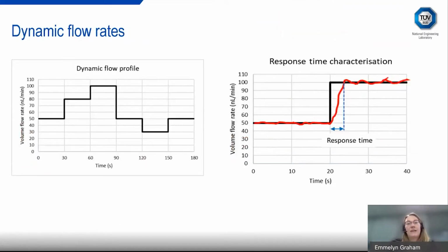There's been a lot of research done for steady flows, but we're actually looking at more challenging, dynamic, fast-changing flow rates within the project. And what I mean by that is that the flow rate can change over a period of less than a second. And what we want is our facilities or our calibration techniques to be able to track and monitor if there are fast changing flow rates. And this is because we want the techniques to be able to identify and track if there are any spikes in the dosage of drugs.